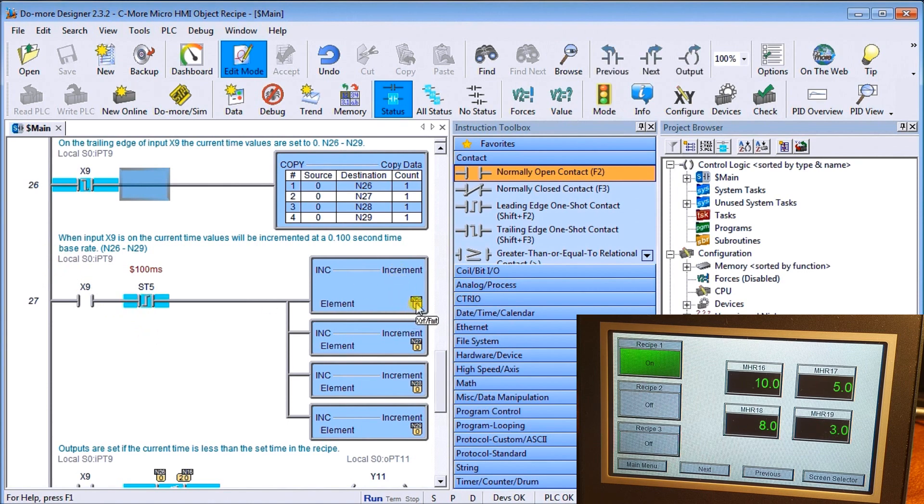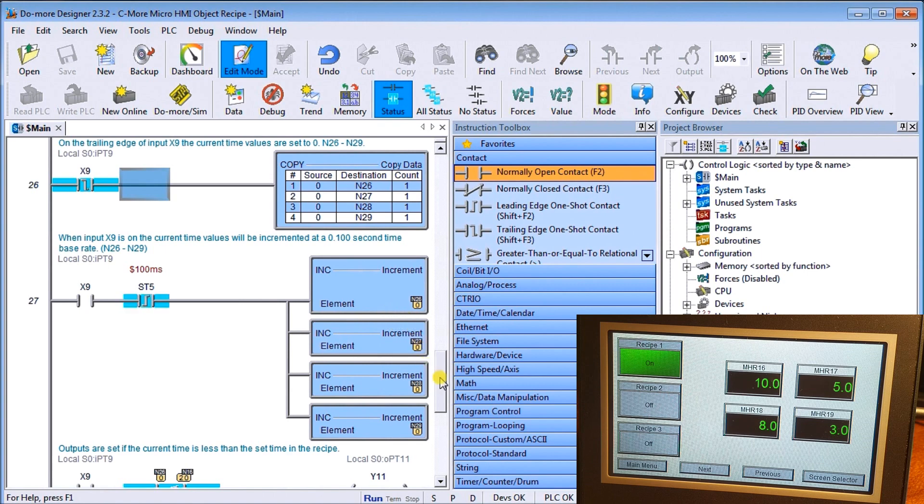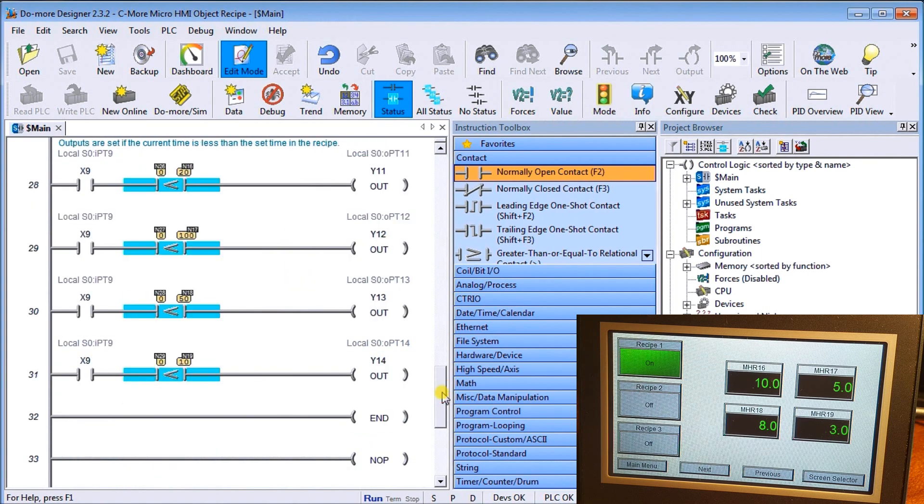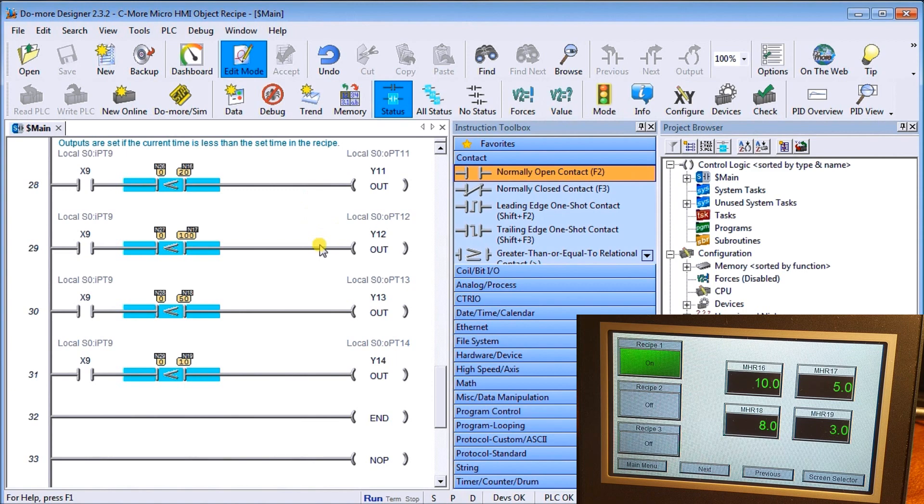Then when X9 is on, we take our 100-millisecond pulsing flag on the leading edge and we will increment N 26, 27, 28, 29. So that will actually give us our count value. Then we take a look at our outputs and we compare our present value to our set value for each of the outputs: Y11, Y12, Y13, Y14, and it will set it accordingly.